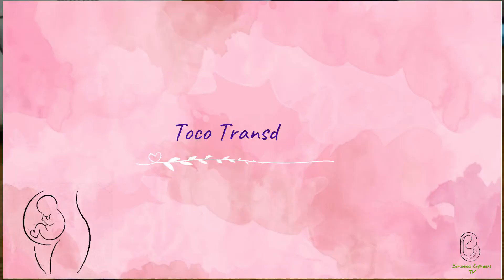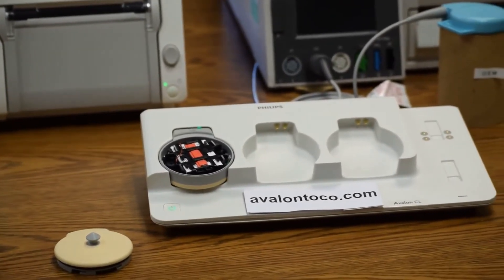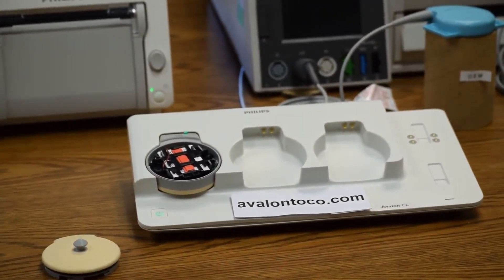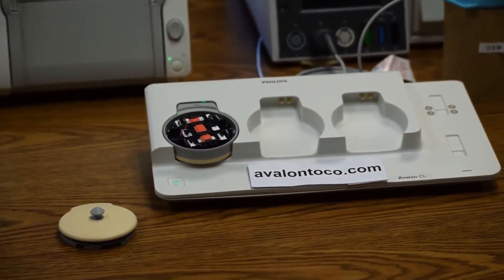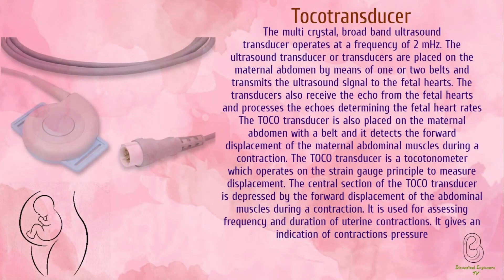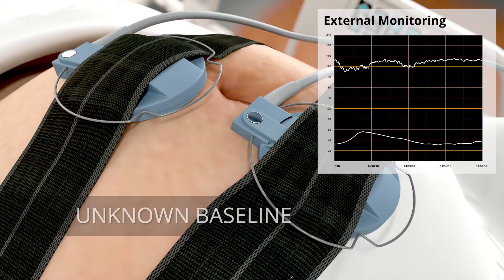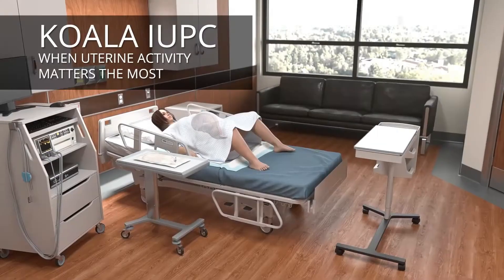A tocodynometer, or TOCO for short, is a transducer pressure-sensing device that detects changes in the abdomen as the uterus tightens during a contraction. It marks how often contractions occur and the length of each, producing a graph that looks like a series of hills rolling across the bottom of the printout. The external contraction monitor cannot tell how strong a contraction is, since the size of the hill is affected by the tightness of the belt and whether the patient is thin or heavy. If a precise measurement of contraction strength is needed, an internal pressure monitor can be placed inside the uterus.